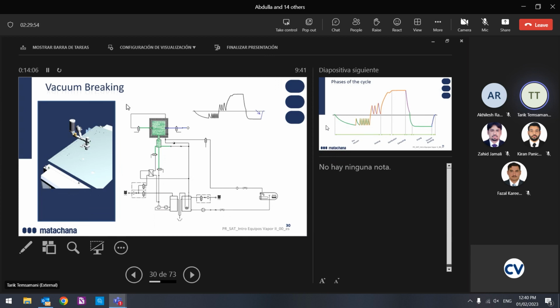In this circuit we have only the filter, the one-way valve and the pneumatic valve. After a while you need to replace the pneumatic valve and the one-way valve, because sometimes they get stuck and we will not reach atmosphere. The door not working can be one of the reasons too. We find this often, and finally you will find it. This is easy to check.